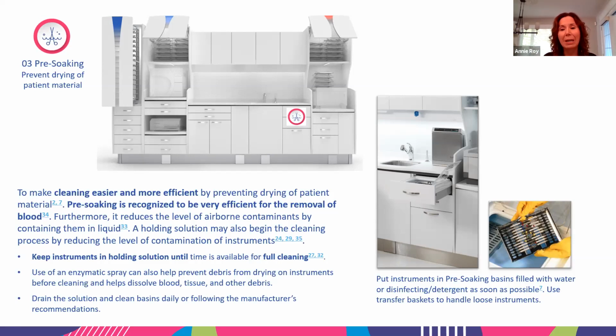If you use a spray, you can keep those instruments in a liquid, or in waterproof drawers or waterproof storage. If you're using any liquid in a container, a drawer, or a basin, you should drain the solution and clean the basins daily or following the manufacturer's recommendations. For loose instruments, ideally, you should try to use a transfer basket, which will avoid handling sharp instruments that are still potentially contaminated. Again, puncture-resistant gloves should be used to transfer instruments from pre-soaking to the ultrasonic cleaner or the dental washer.